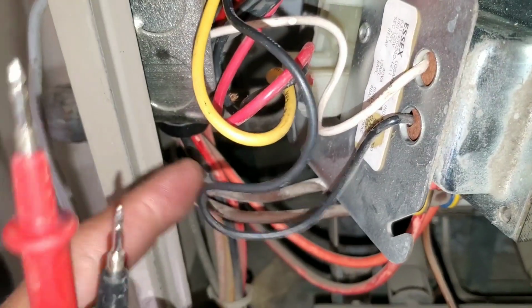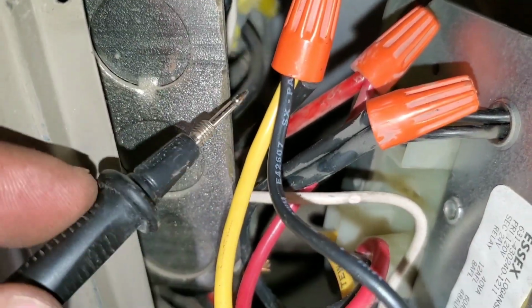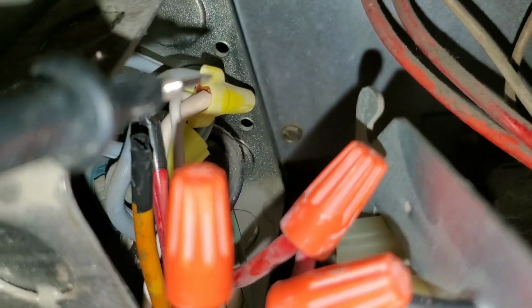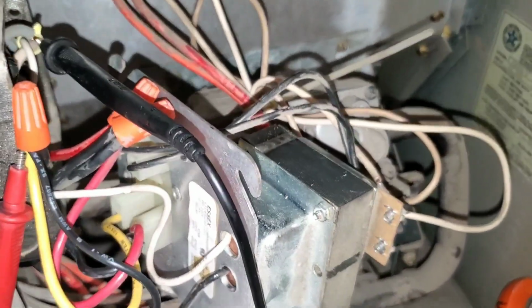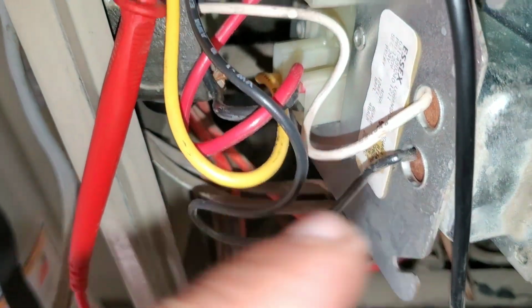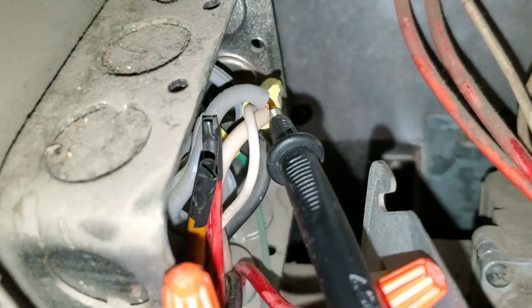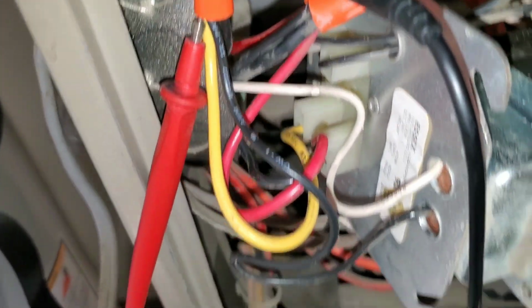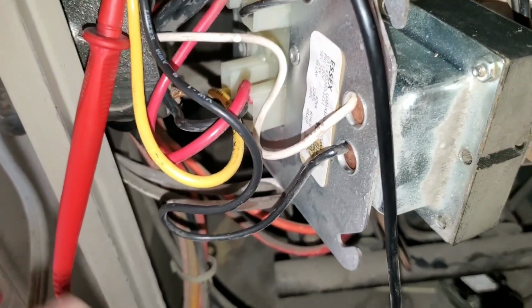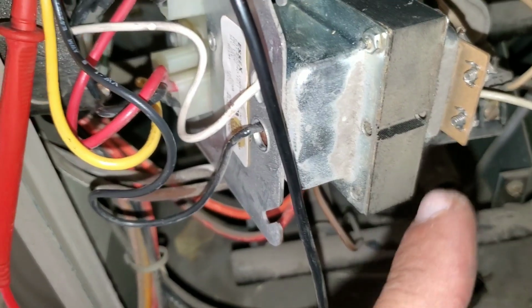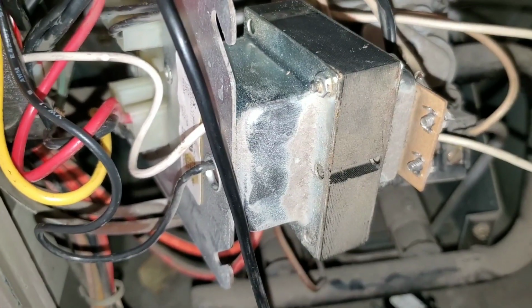So you want to follow those leads. You have your black here. This will be your incoming 120 volts, and this is going to be your neutral. So you want to trace your neutral. Again, please be very careful when you're working on electrical. So here I have my multimeter set to volts AC. Right now I have one of my leads going into my 120 volts that supply the necessary voltage to my transformer, as well as one of my leads on my neutral. So at this point, if you do see that you have 120 volts and you're not getting the proper voltage on your low voltage, you are going to have to replace the transformer.